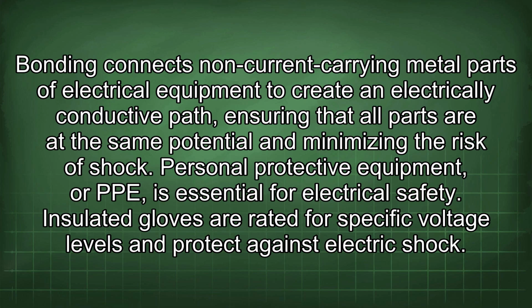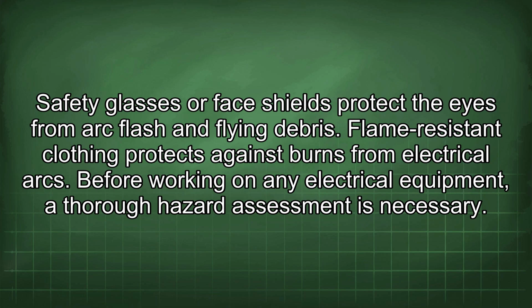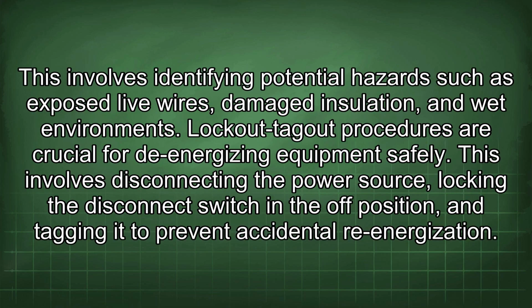Personal protective equipment, or PPE, is essential for electrical safety. Insulated gloves are rated for specific voltage levels and protect against electric shock. Safety glasses, or face shields, protect the eyes from arc flash and flying debris. Flame-resistant clothing protects against burns from electrical arcs. Before working on any electrical equipment, a thorough hazard assessment is necessary. This involves identifying potential hazards such as exposed live wires, damaged insulation, and wet environments.